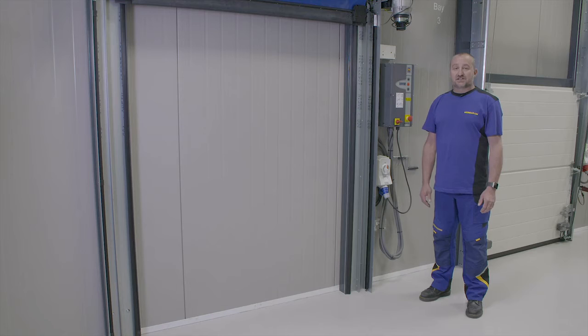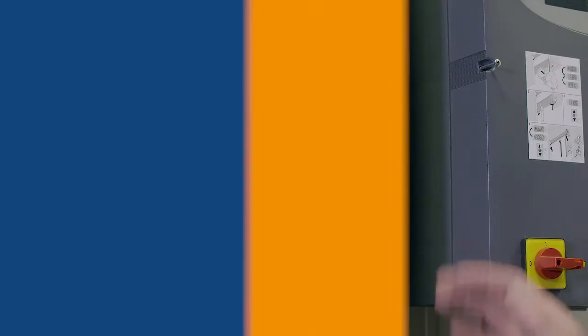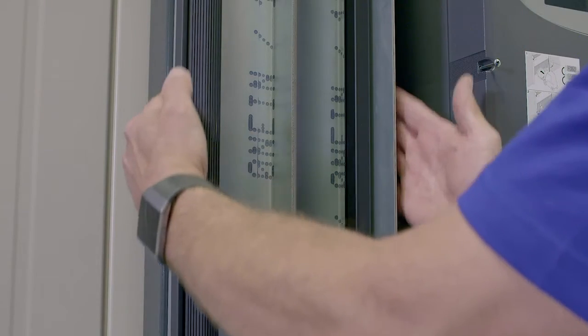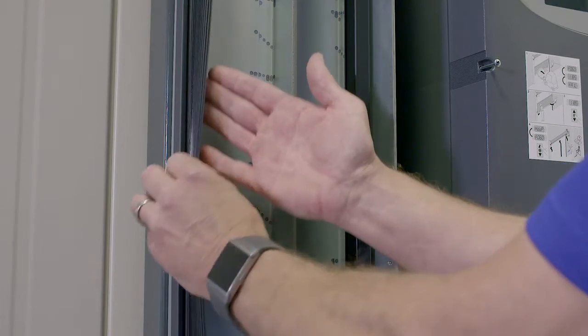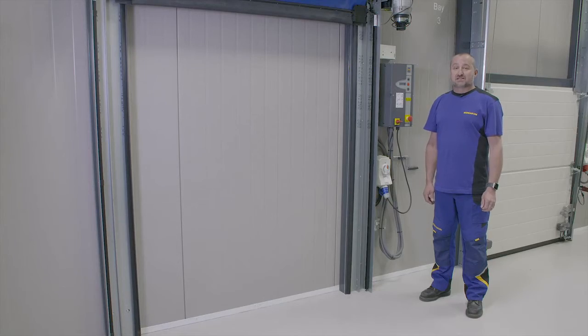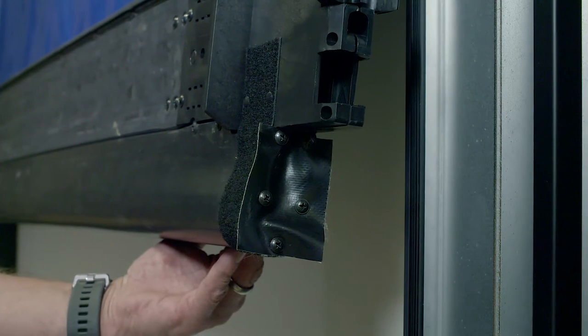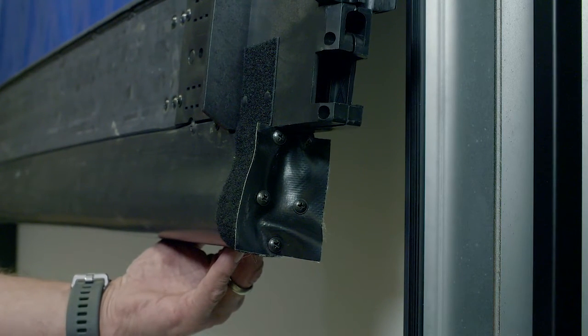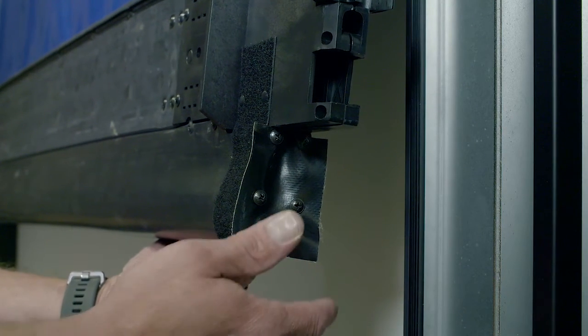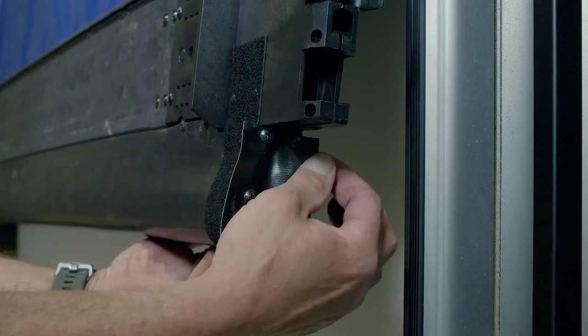From here, you can check if there's any damage to the guides, the legs, the leg covers or the side seals. You can easily inspect the bottom edge with the leg covers off. Check that the PVC end pieces on the bottom rail are intact and there's no debris hanging off them.